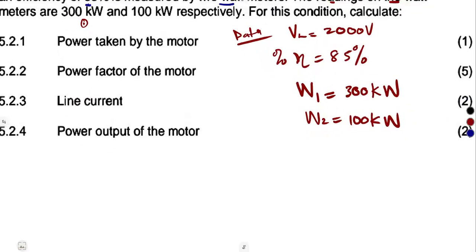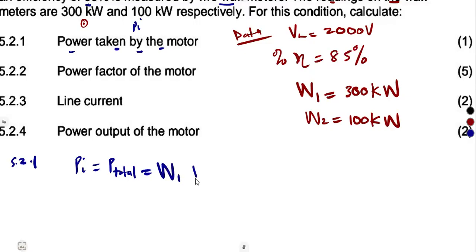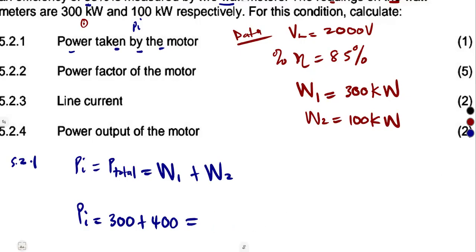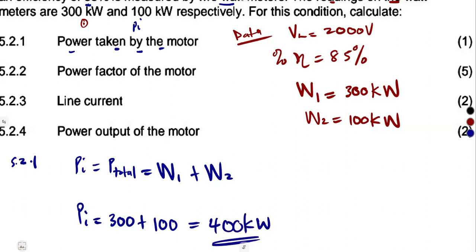For part 5.2.1, calculate the power taken by the motor. The power taken is the input to the motor, which is our total power — the sum of the two watt meter readings. So watt meter one plus watt meter two: 300 plus 100 gives us 400 kilowatts.